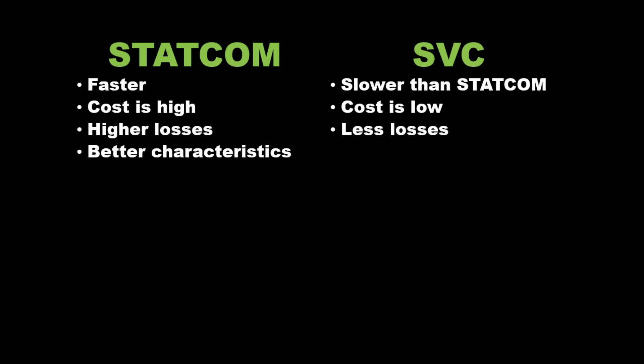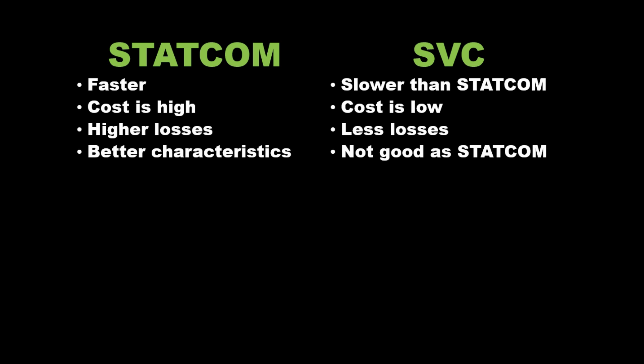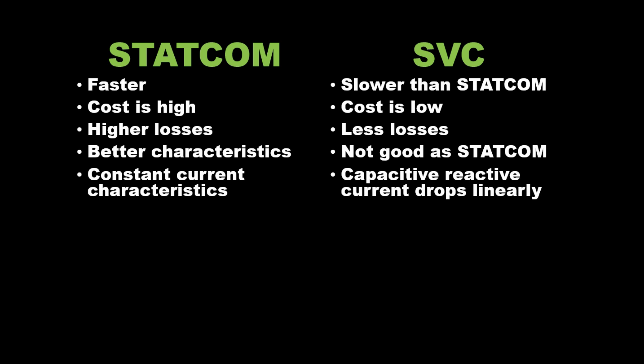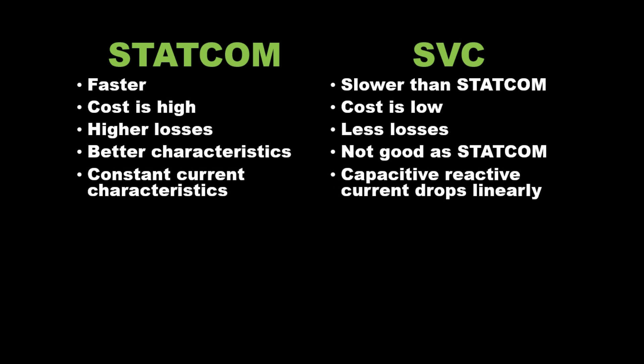StatCom has better characteristics than SVC. StatCom has constant current characteristics when the voltage is low and under the limit, whereas in SVC the capacitive reactive current drops linearly.